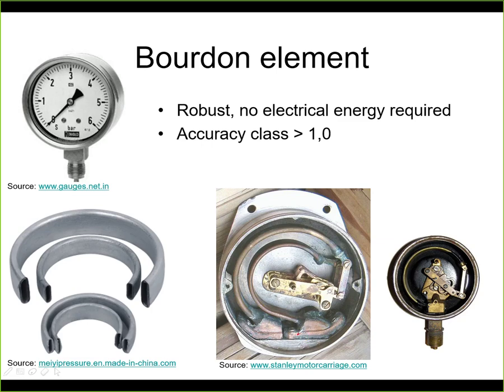for the pressure sensing. Here on this picture you can see just one Bourdon tube, so this is a pressure gauge to measure one pressure. Again, this is the input port, this is the Bourdon tube, and this is the sealed end, and through this lever and this lever and this gear the motion is transferred. So when you increase the pressure inside, this Bourdon tube tries to flatten itself, so it tries to move upwards in this picture, and then this motion is visible on the needle.